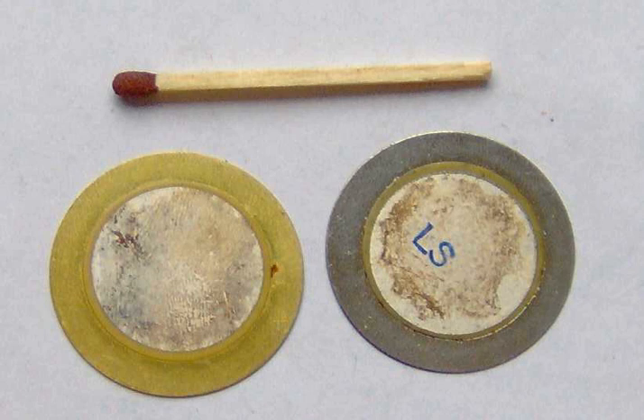Additionally, piezoelectric technology is insensitive to electromagnetic fields and radiation, enabling measurements under harsh conditions. Some materials used, especially gallium phosphate or tourmaline, are extremely stable at high temperatures, enabling sensors to have a working range of up to 1000 degrees Celsius.